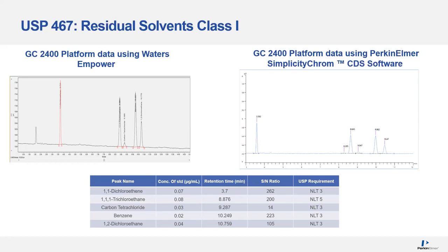Looking at the table, let's focus on benzene. The specification is not less than 3 for signal-to-noise, and we see benzene is significantly higher — approximately 70 times. With benzene and some of the other chlorinated compounds, detection is not an issue at all. You will see a significantly diminished response for carbon tetrachloride, which appears around nine minutes on the right-hand chromatogram. The spec is not less than 3, and we get consistent values around a 14 signal-to-noise ratio — making it very easy to integrate and get accurate results.